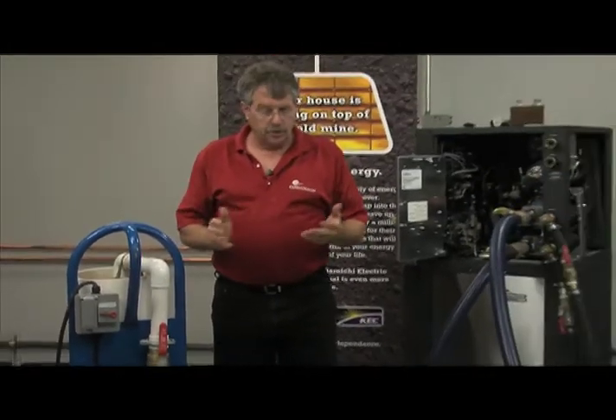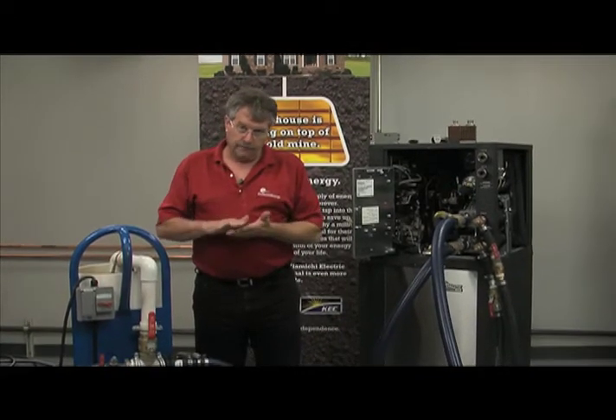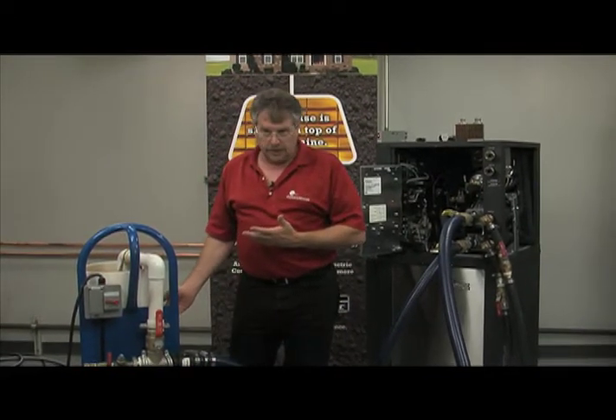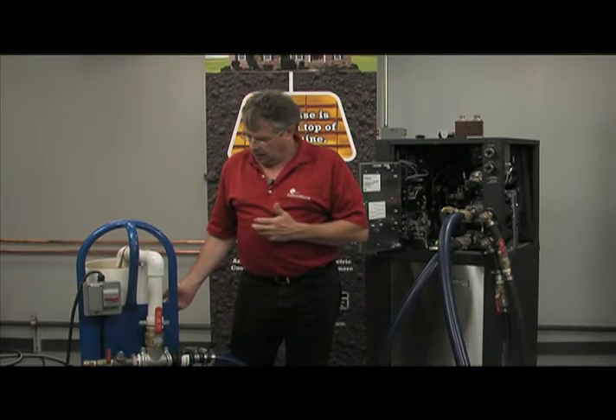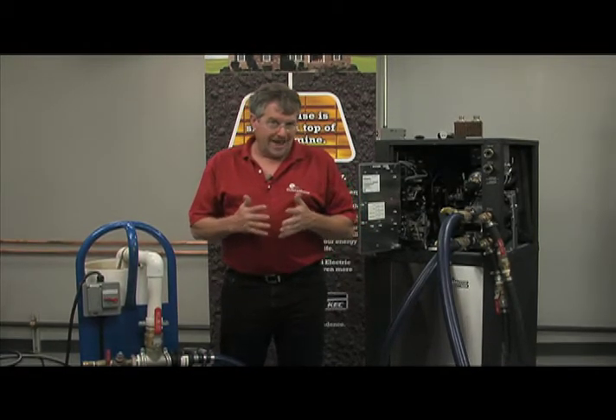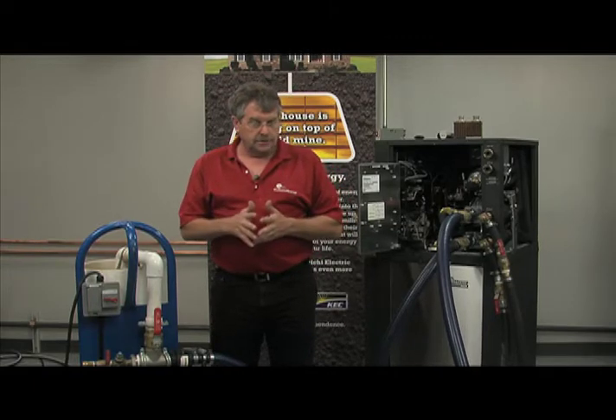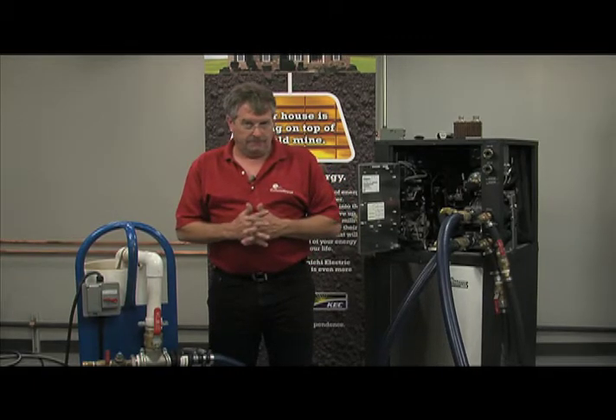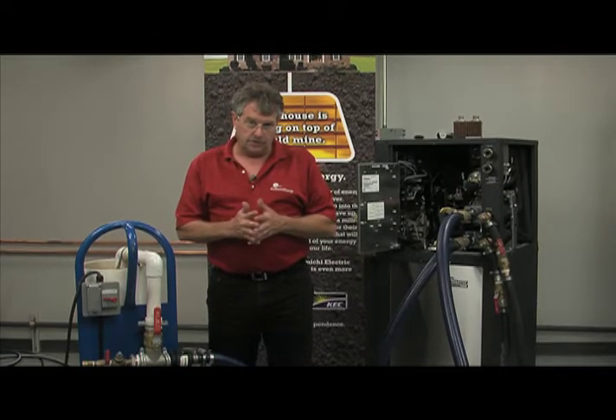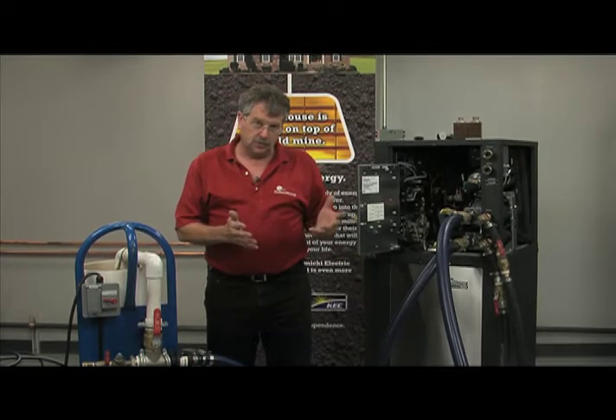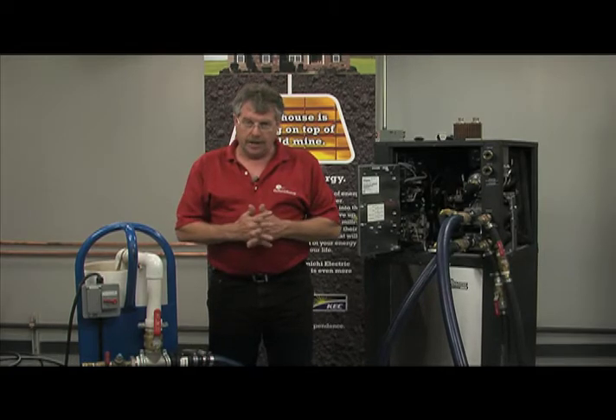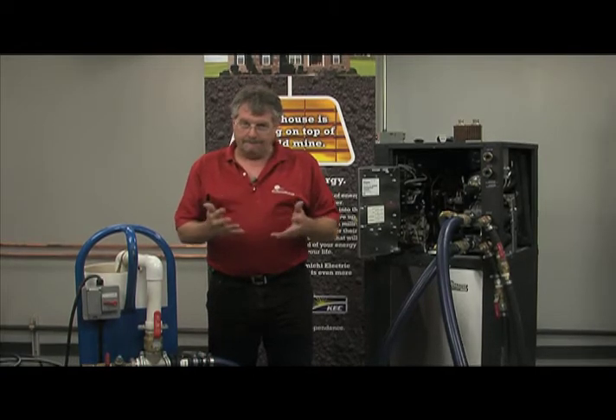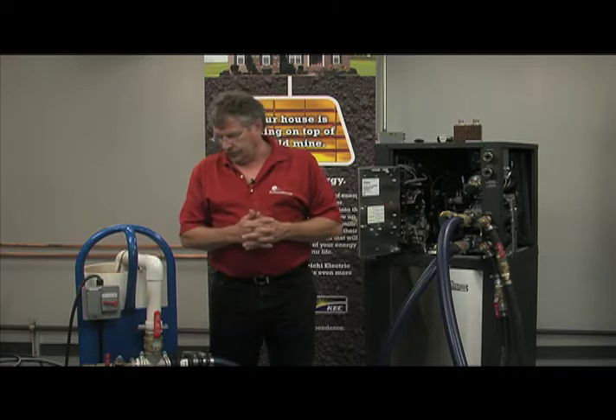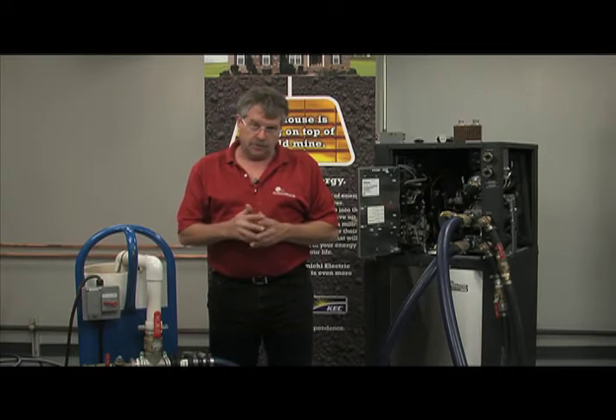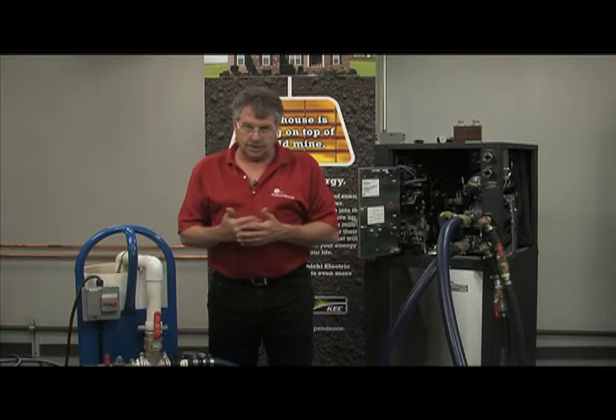Now that we've circulated both through the heat pump and the loop field for some period of time, we're going to go through a couple of compression tests looking for our fluid drop through our sight glass and the indicator. We're using an O-ring on our indicator. That is the only true measure whether we have successfully moved that air out. And remember, guys, got to have at least minimum, absolute basement, 2 feet per second velocity going through that entire loop field, as well as your internal components, to remove that air. You're not going to dislodge the air just by saying, oh gee, I don't see any more bubbles coming back, or I've been flushing for 30 minutes. The only true validation is compression test, fluid drop.